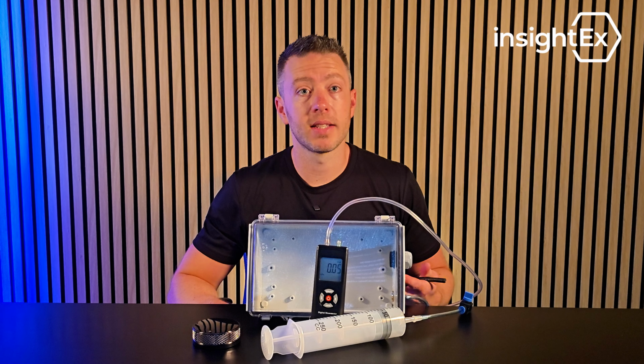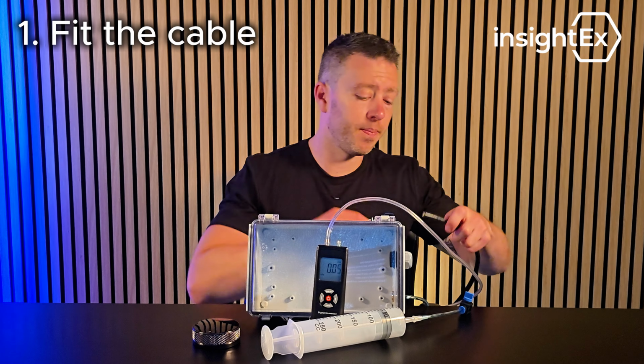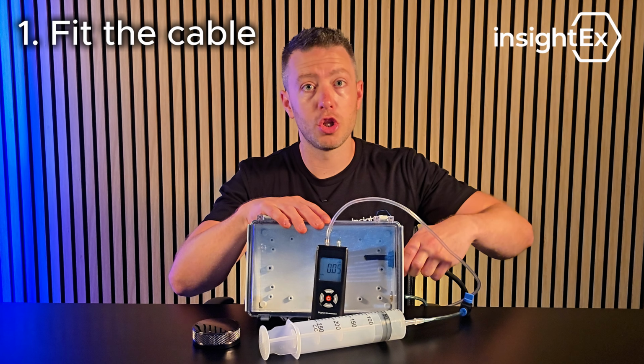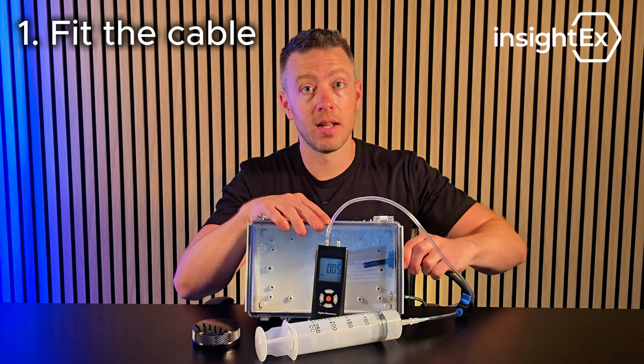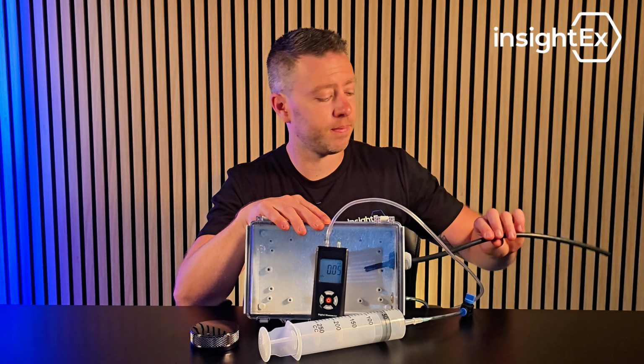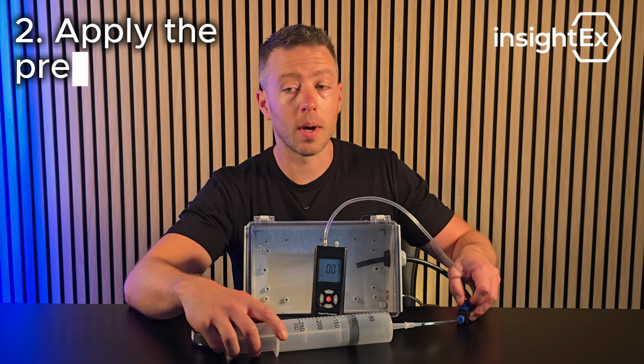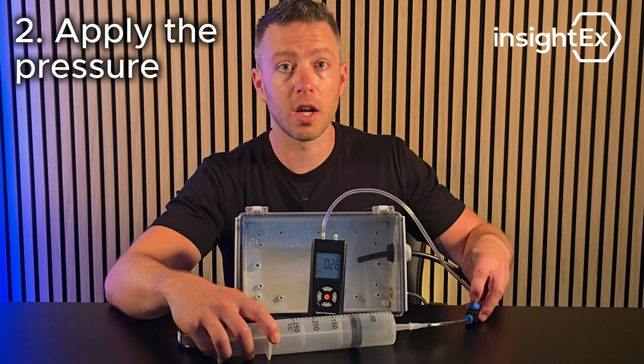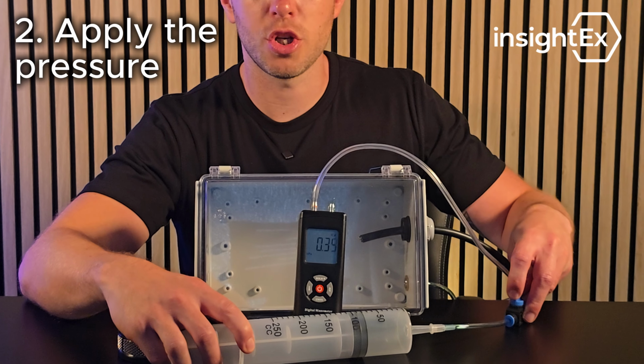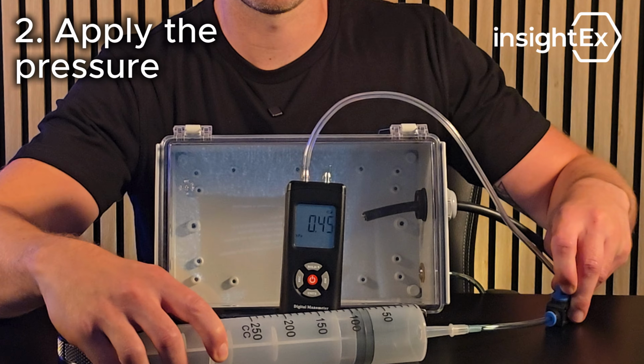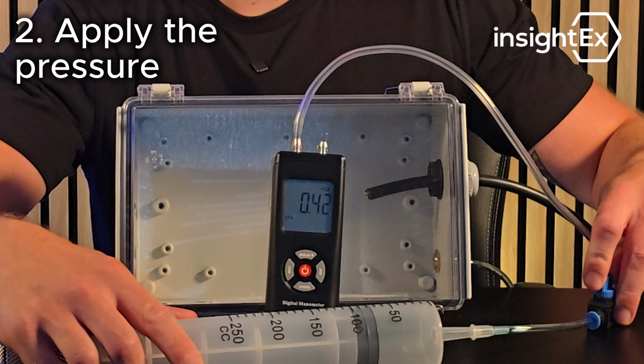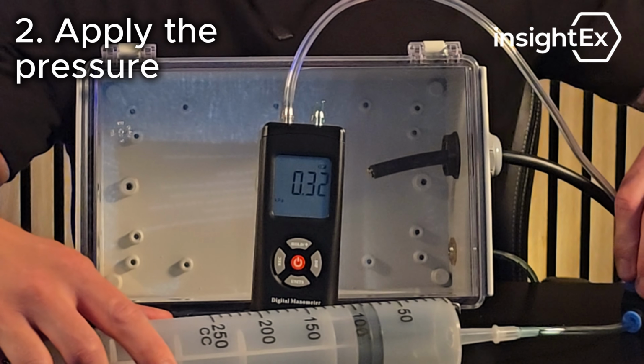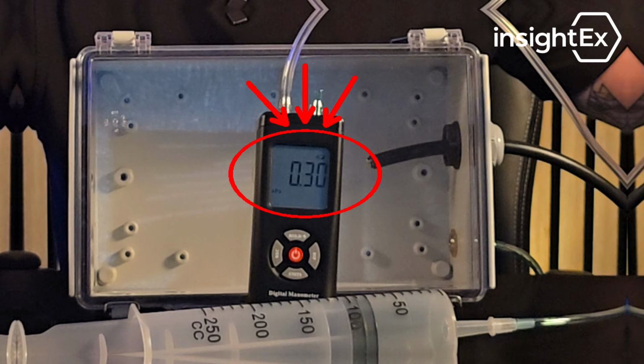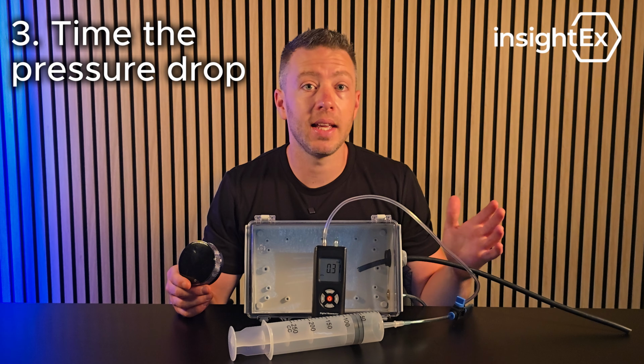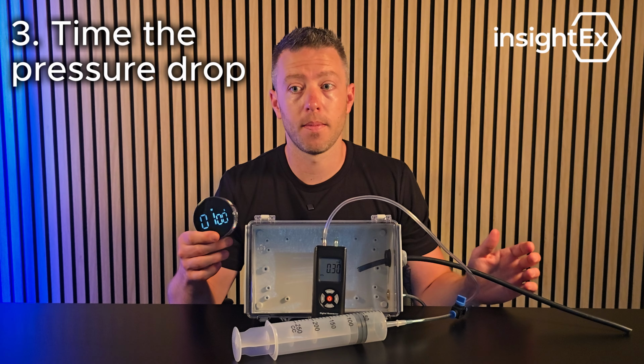So let's run through a test. First, you fit the cable and you want to be applying just enough pressure to seal around the outside. Second, you apply the correct amount of pressure and close the valve. So you want to be hitting just above 300 pascals. Then you measure the time it takes to drop the pressure.